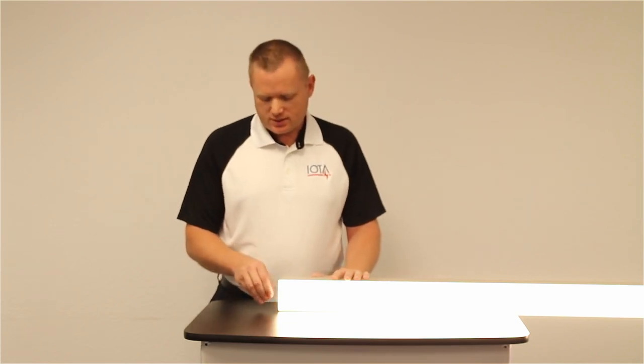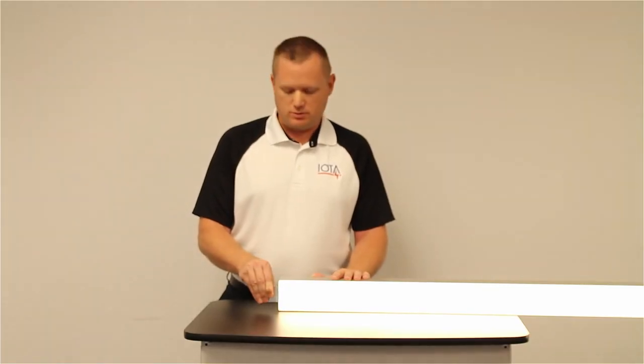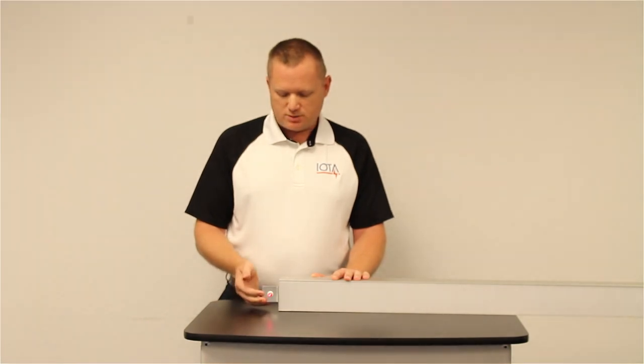To perform a test, simply push and hold the test button. You will see the fixture transition from normal mode to emergency mode. When you release the test button, the fixture will have a short delay and then transition back to normal mode.